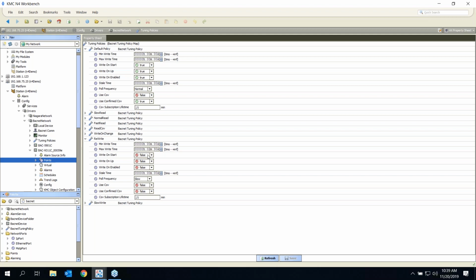It could be that there's an issue on the bus. It's polling slower than expected. It could be that there's a lot more objects being polled, which is causing the cycle time to be longer. It could be any number of things that might be causing it. I would say use a little bit of caution. A couple of things to consider. A lot of the components in the wire sheet logic have functionality where they'll look at status and might ignore an input with a bad status like stale. So if you're running it into an average block, the average block might ignore the point value if it has a stale status. So you need to be cognizant of what logic you're doing and what that impact might be on your control logic.